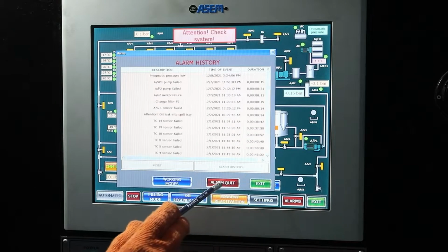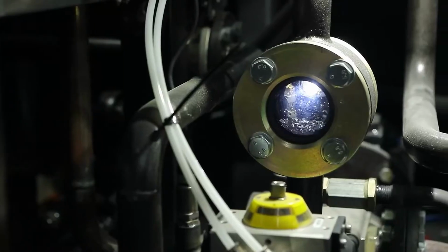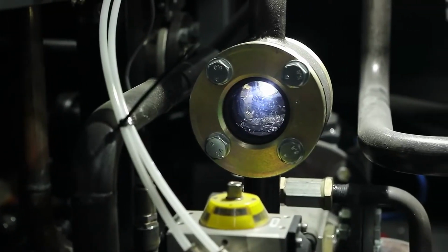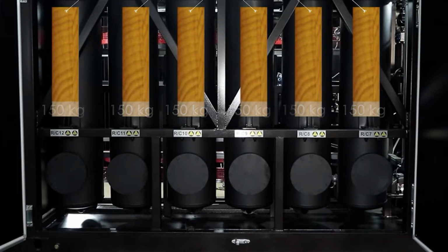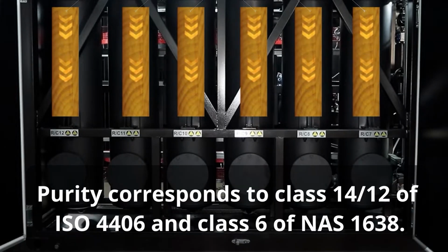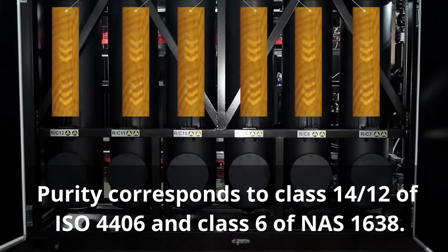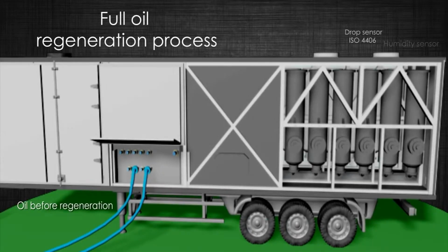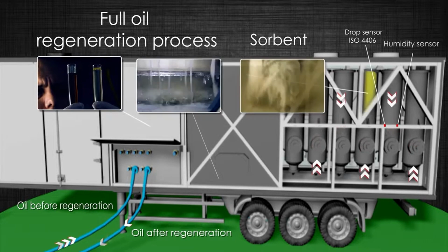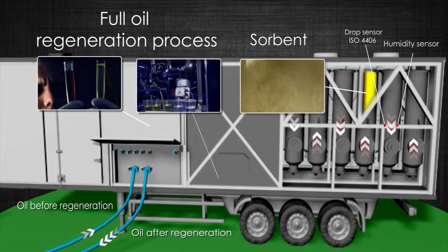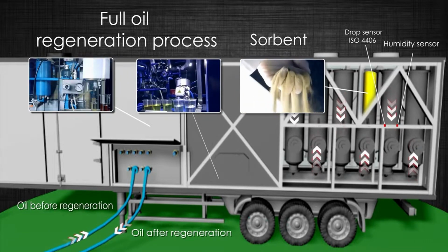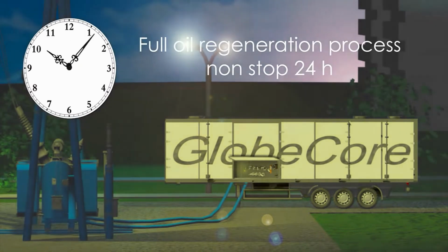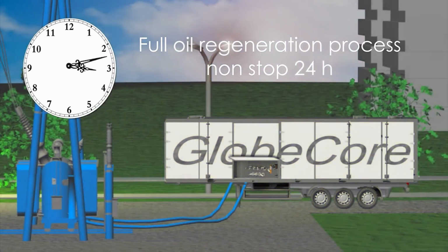After two-stage regeneration using GlobeCore technology, waste turbine oil is reclaimed to as good as new condition, and its purity corresponds to Class 14/12 of ISO 4406 and Class 6 of NAS 1638. The use of GlobeCore technologies for turbine oil regeneration allows saving money on the purchase of new oil and disposal of waste oil, enhancing the reliability of power-generating equipment, and extending the repair intervals.